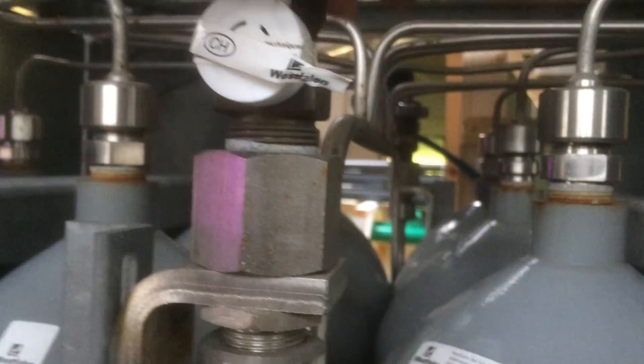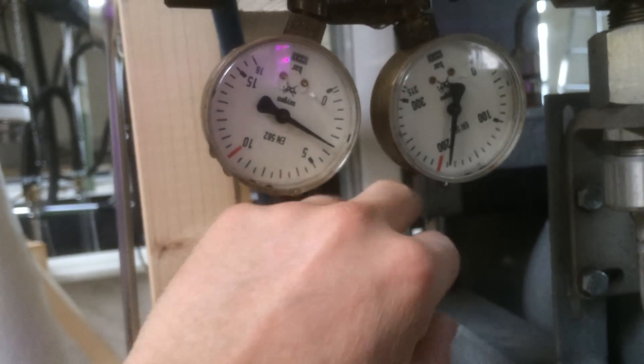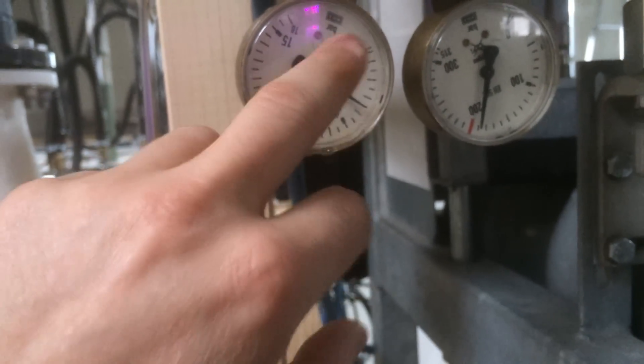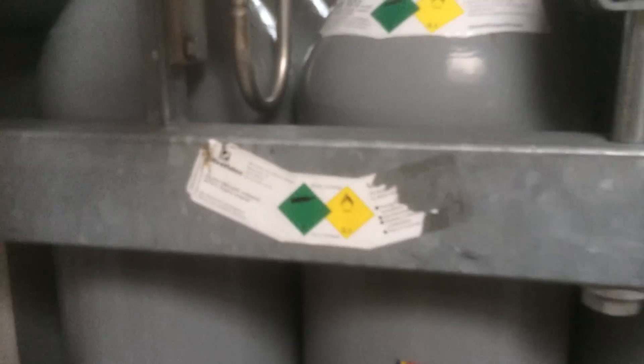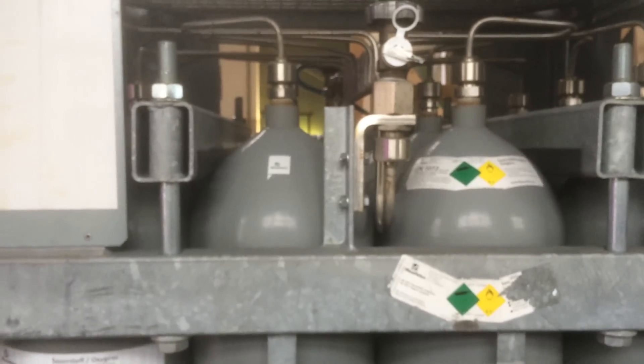Anyway, they're all connected together so it's just one tap - you can draw from either side. You run all 12 bottles at the same time. These are 200-bar cylinders, filled up to about 220-240 bar, and now down to just under 200 - that's about 3 to 4 days of running. The whole system maintains constant pressure as it slowly goes down. What's great is they're all connected; I can combine this bundle to the next bundle down there, or connect 20 or 30 together. The risk of running out of oxygen is much much lower, and I only need to refill once every 3 months or so.